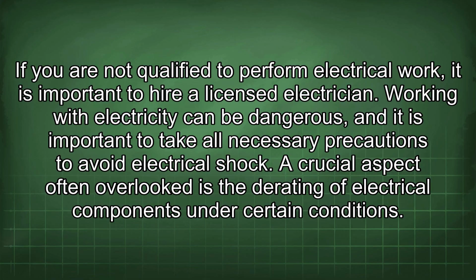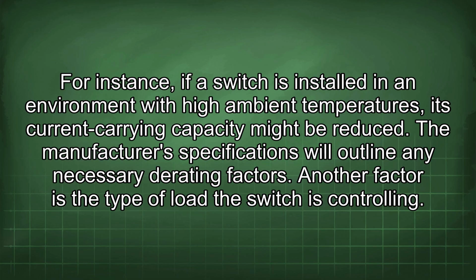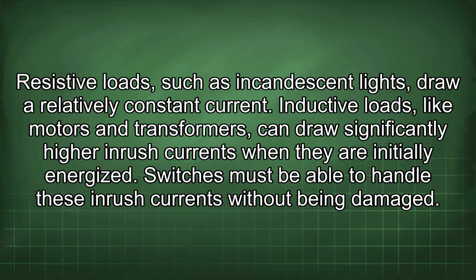A crucial aspect often overlooked is the derating of electrical components under certain conditions. For instance, if a switch is installed in an environment with high ambient temperatures, its current carrying capacity might be reduced. The manufacturer's specifications will outline any necessary derating factors. Another factor is the type of load the switch is controlling. Resistive loads, such as incandescent lights, draw a relatively constant current. Inductive loads, like motors and transformers, can draw significantly higher inrush currents when they are initially energized. Switches must be able to handle these inrush currents without being damaged.